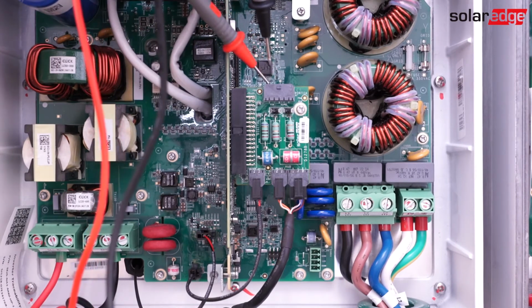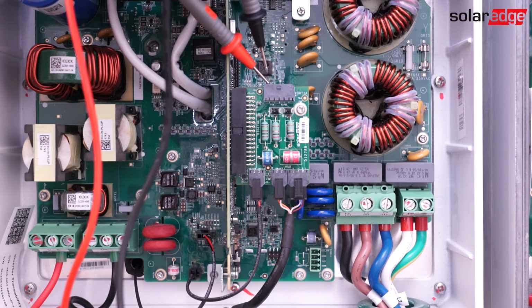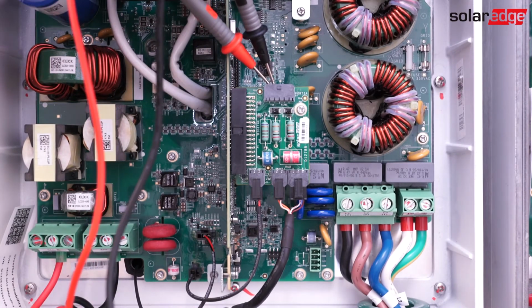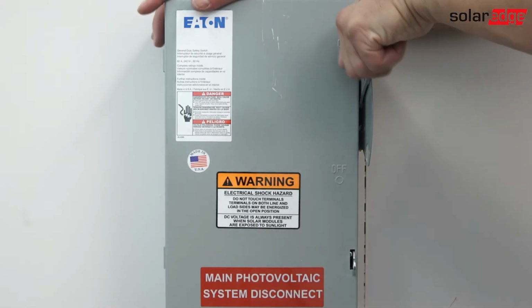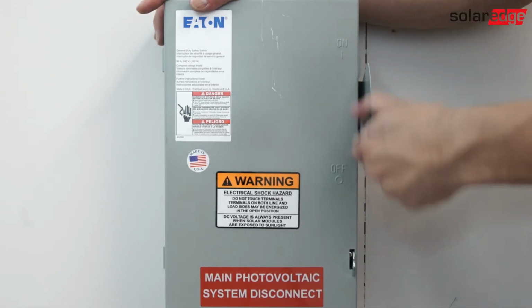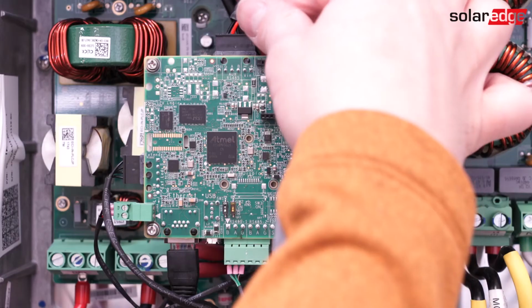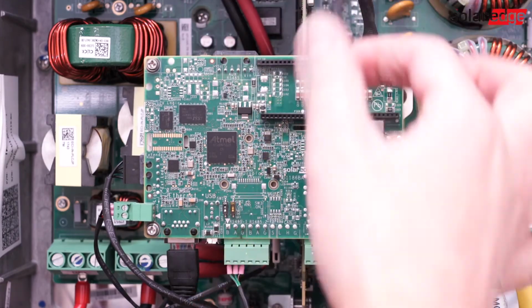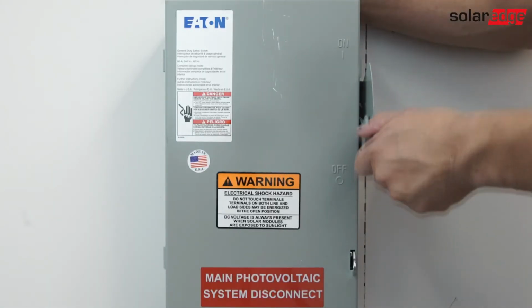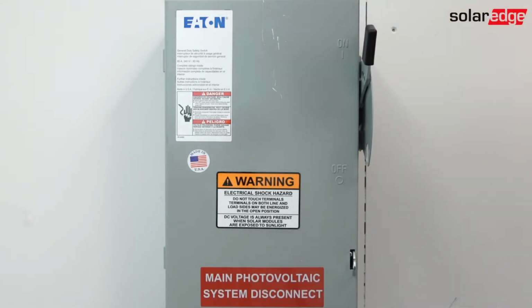On the secondary unit, locate the socket at the top of the communication board and insert your red or positive probe in the leftmost hole and your black or negative probe in the hole directly next to it and record your DC voltage. Expected voltage is between 13 and 18 volts. If no DC voltage is measured, turn off AC power and remove the connector at the top of the communication board in the primary unit. Then turn AC power back on and check inside the connector and record DC voltage.